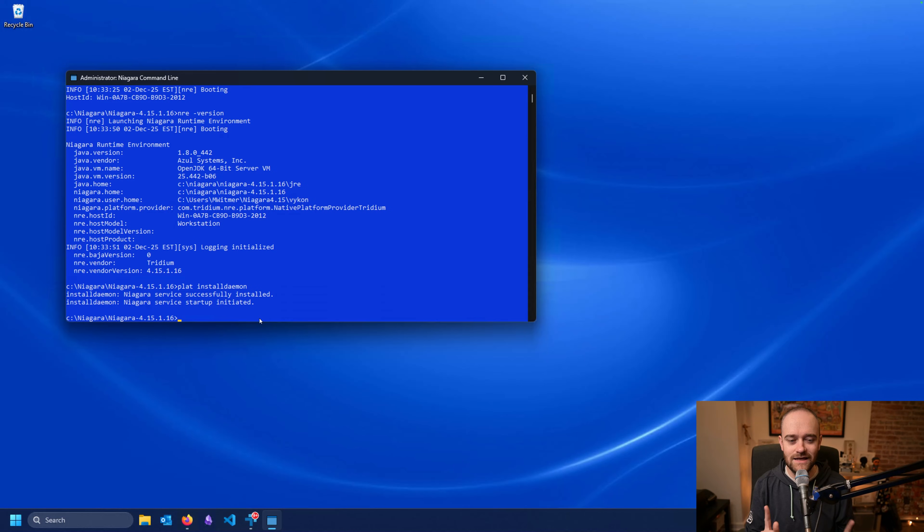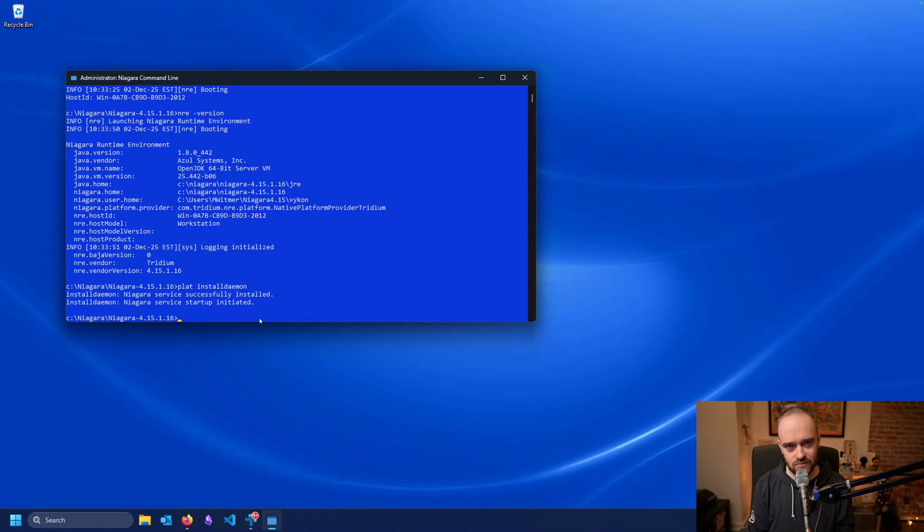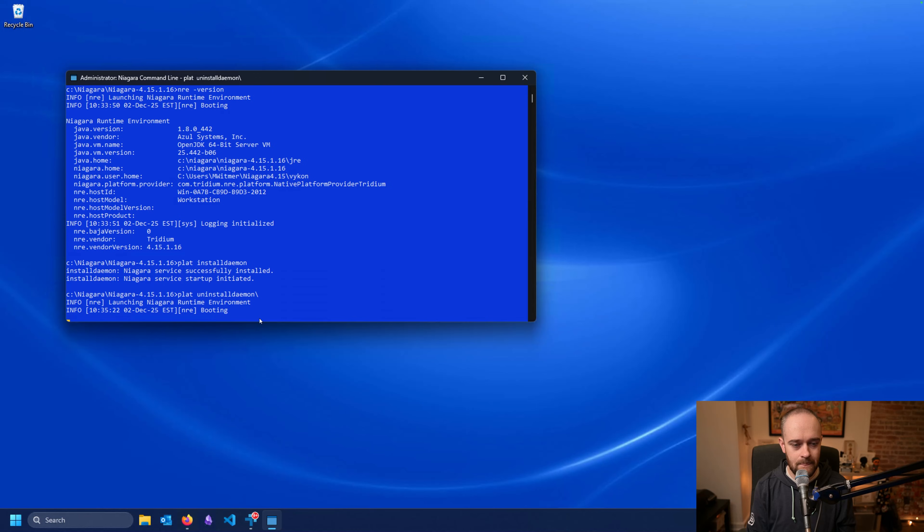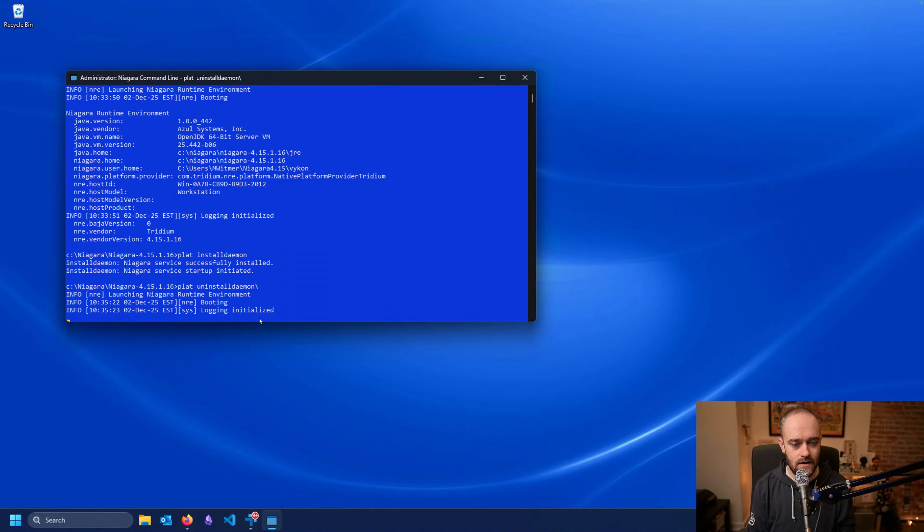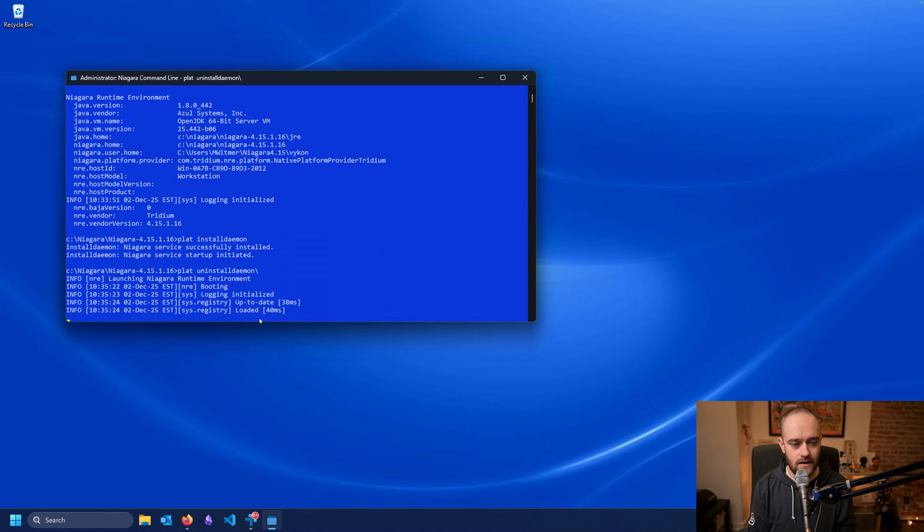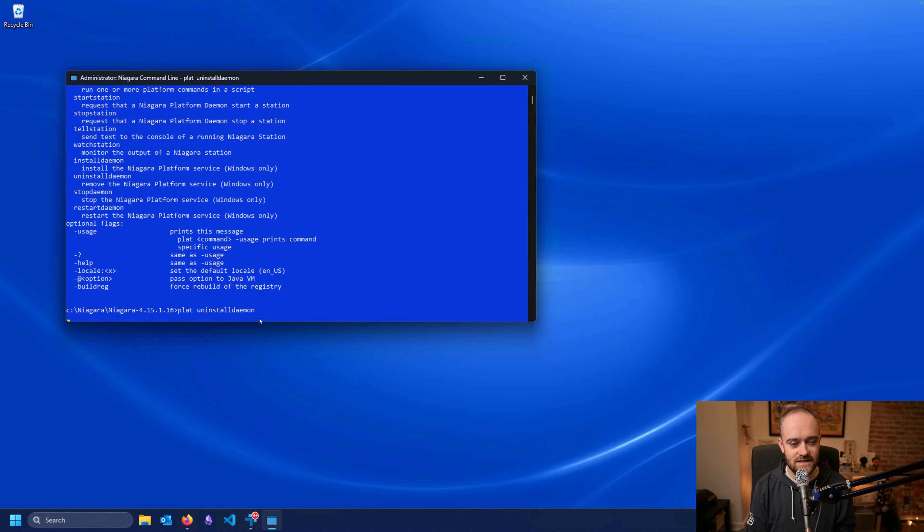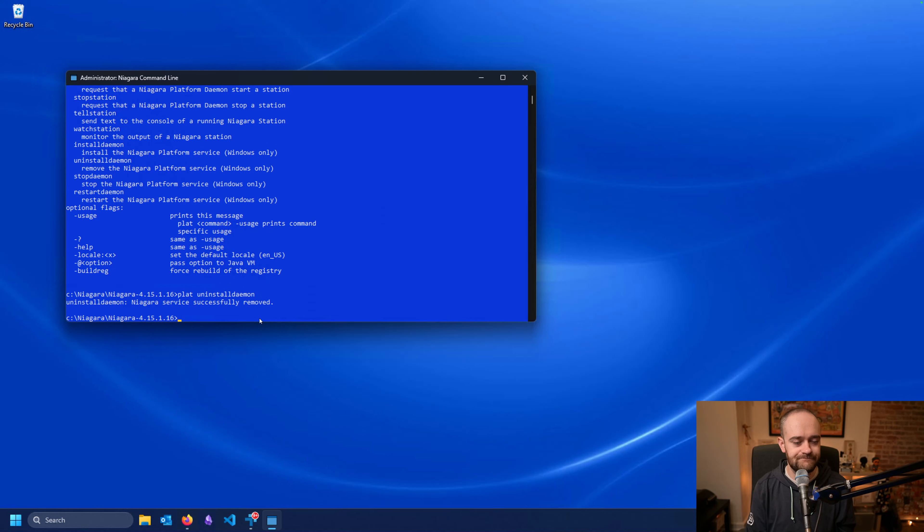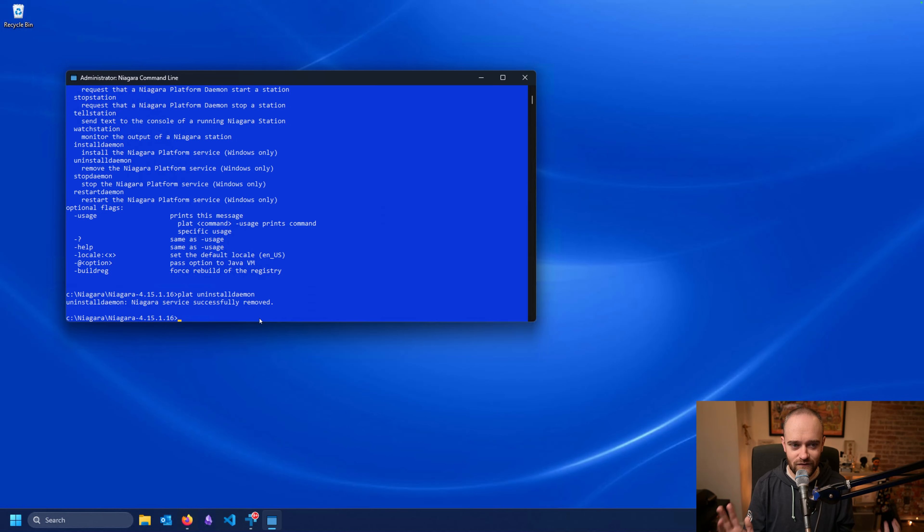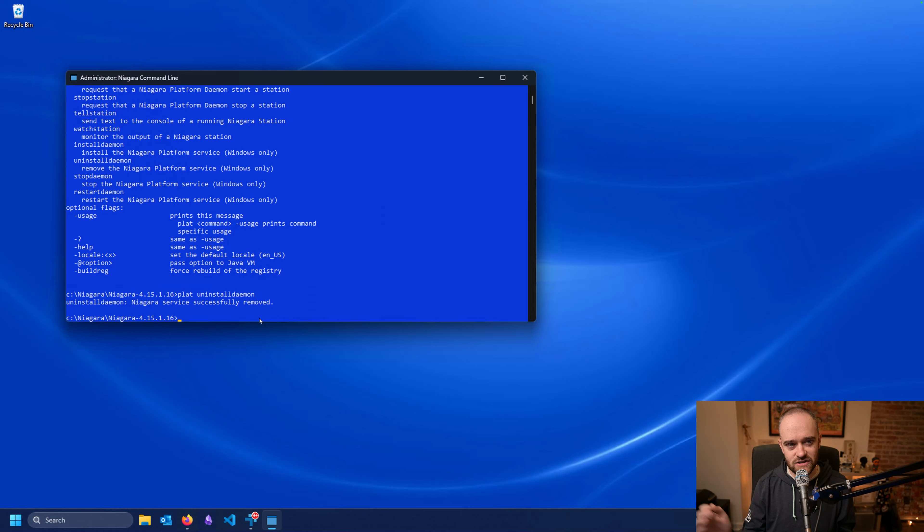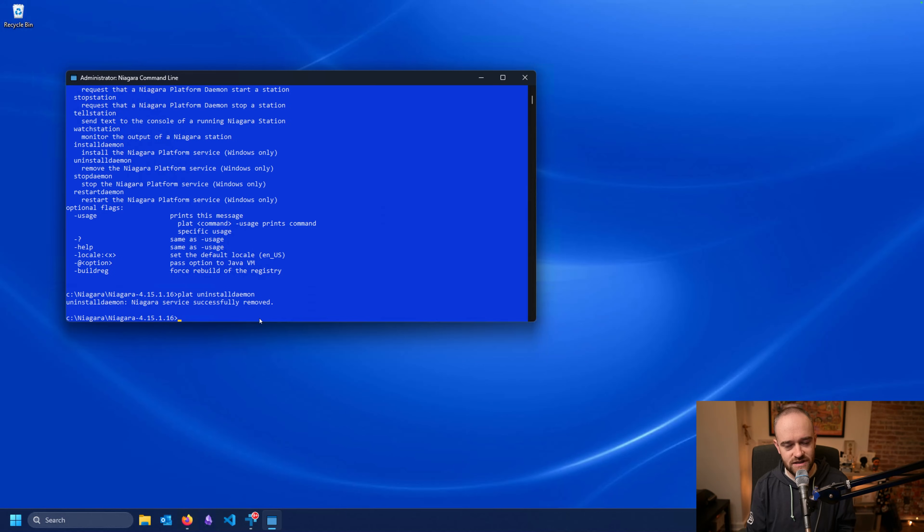As a flip side to our 'install daemon', we can also do an uninstall. So if you had an issue with a particular daemon or you wanted to switch to something else, you could do 'plat uninstall daemon'. And I screwed up here because I put that slash at the end, it got confused because of it. And that time it worked properly because I put in the right flag in the right command. So the Niagara service was removed here, and I could go and install it somewhere else if I needed to, or reinstall it in this particular version if I was maybe having an issue and I was trying to troubleshoot something.